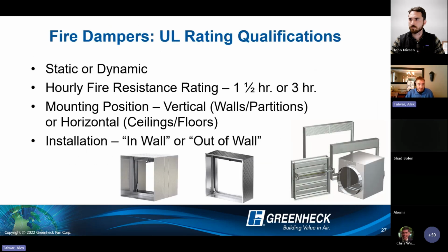So, I kind of touched on this already in terms of static or dynamic. I'll talk about the airflow ratings here in a minute, but the hourly fire resistance rating is certainly important. They come in two types, 1.5 hours or 3 hours. Essentially, that's just how long they are subjected to the UL fire test for. But those are your two damper ratings. I'll talk a little bit about how that applies to the construction and IBC requirements in a minute here.